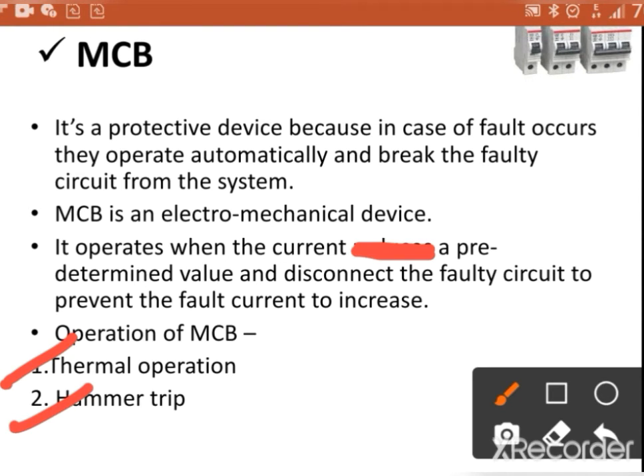In thermal protection, a bimetallic strip is used. Whenever the fault current increases, heat is generated in this strip and the circuit breaker operates. And in hammer type of protection, it uses the magnetic operation of plunger, solenoid and trip lever.